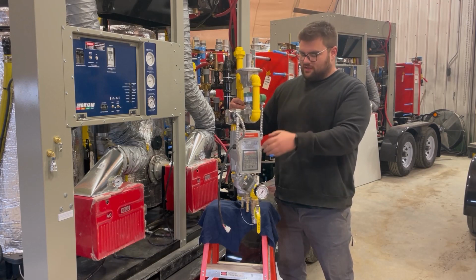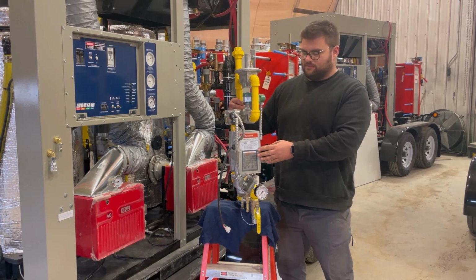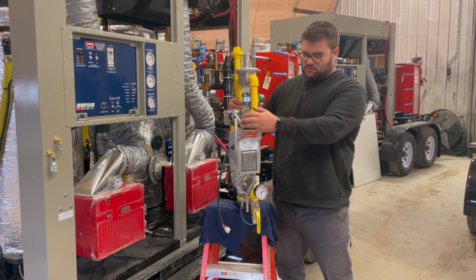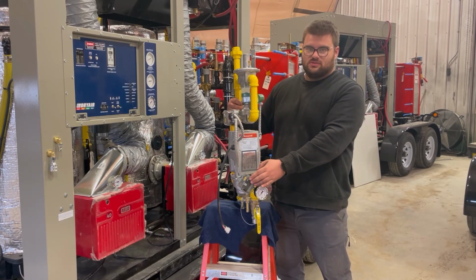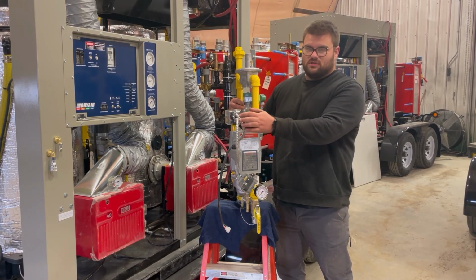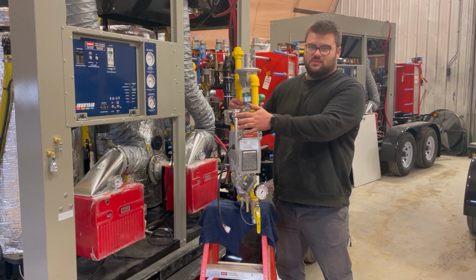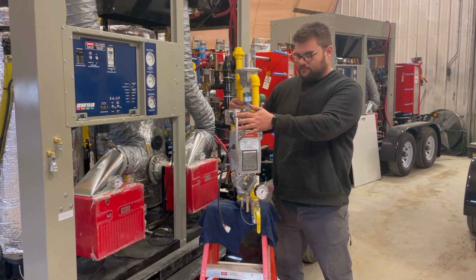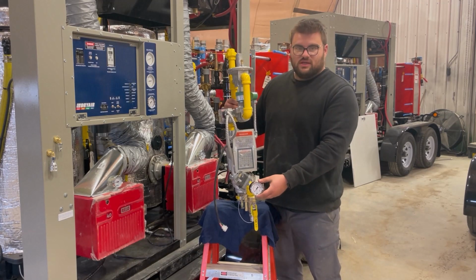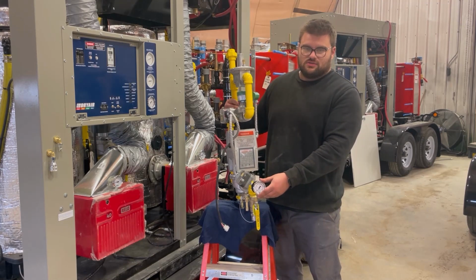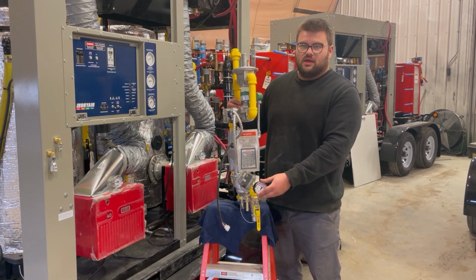You have a redundant valve and a main gas valve, as well as a low gas pressure switch and a high gas pressure switch. On new setups, you're always going to want to reset your low gas pressure switch because there will be air in the gas line. And you have a secondary gauge at the bottom of your gas stream to see what pressure you have going to your burner.